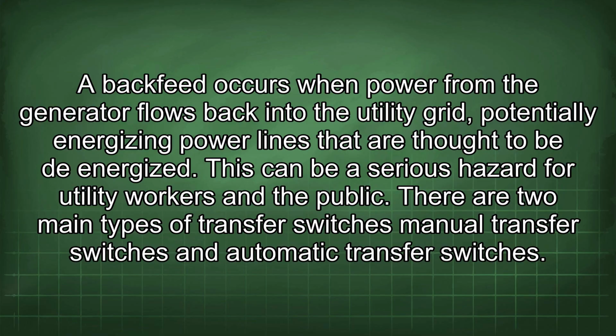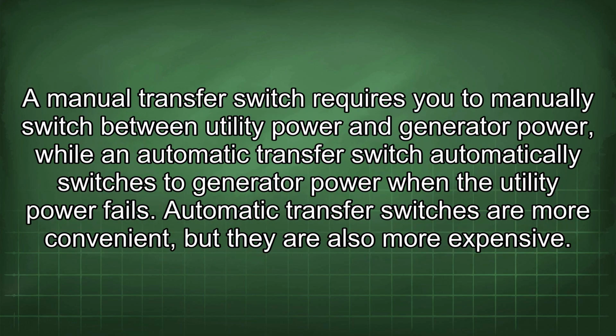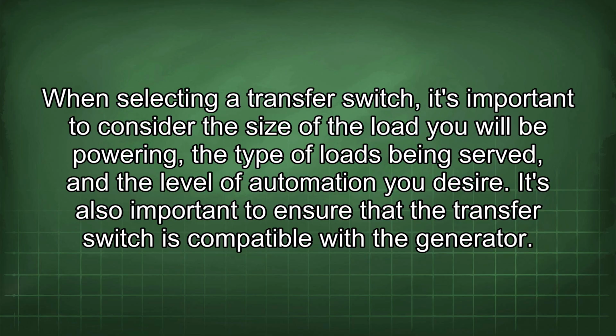There are two main types of transfer switches: manual transfer switches and automatic transfer switches. A manual transfer switch requires you to manually switch between utility power and generator power, while an automatic transfer switch automatically switches to generator power when the utility power fails. Automatic transfer switches are more convenient, but they are also more expensive. When selecting a transfer switch, it's important to consider the size of the load you will be powering, the type of loads being served, and the level of automation you desire. It's also important to ensure that the transfer switch is compatible with the generator.